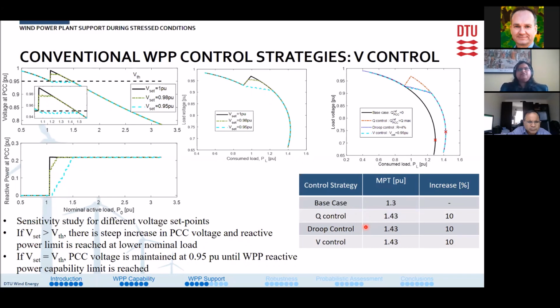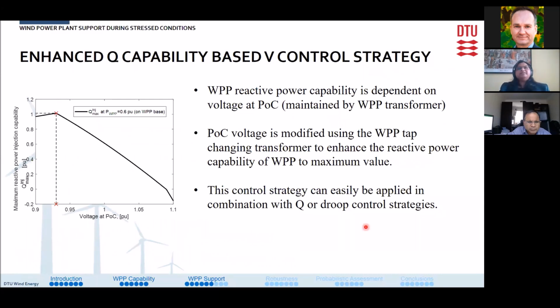So this motivated us to investigate the enhancement of this capability in order to provide better support to the grid. Now, as discussed previously, the wind power plant capability is both active power and voltage dependent. So if we choose a constant active power, any operating point, and see the relation between the voltage and the reactive power capability, then we can get something as shown in the figure here.